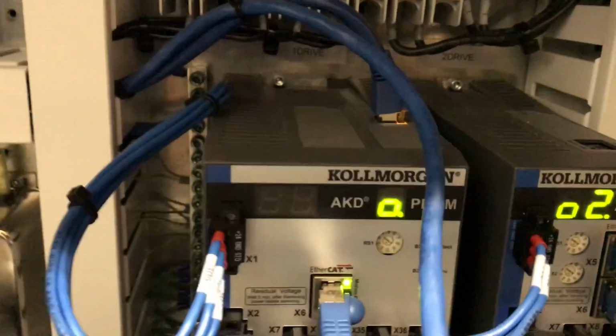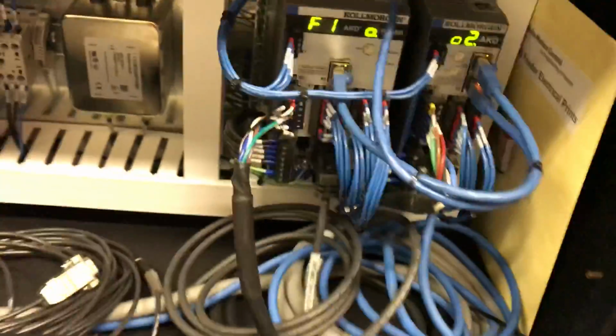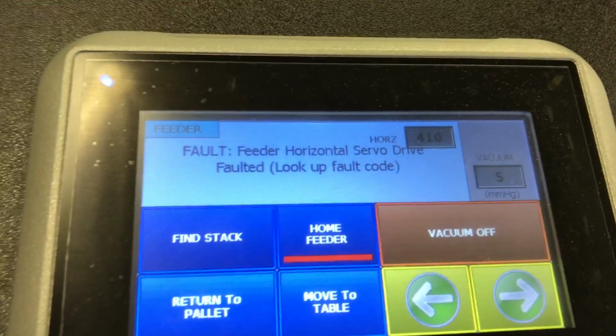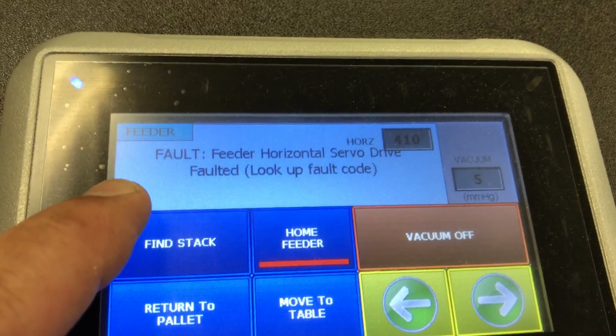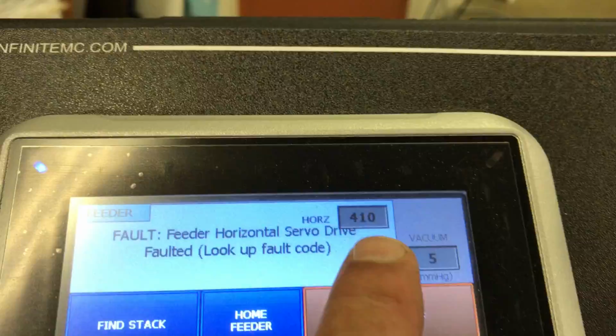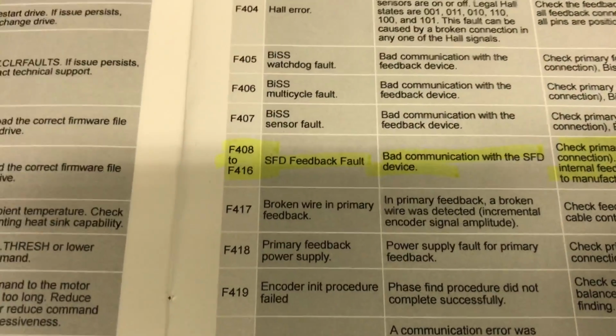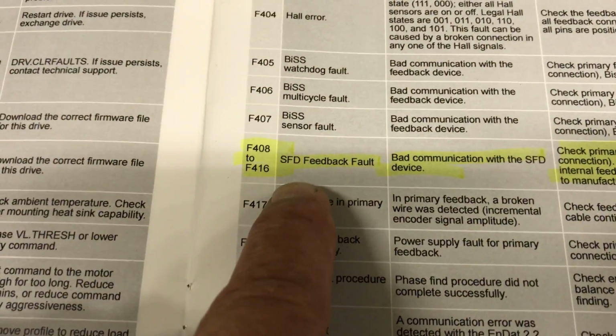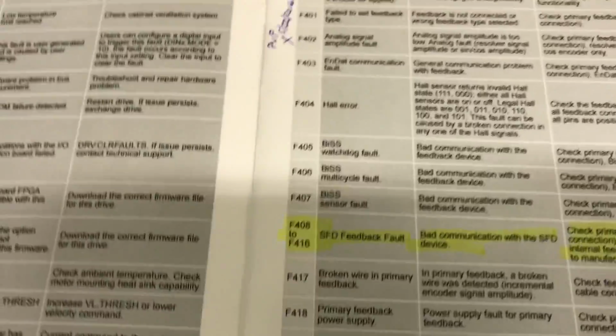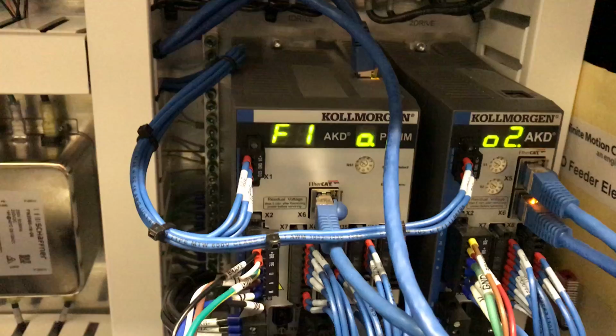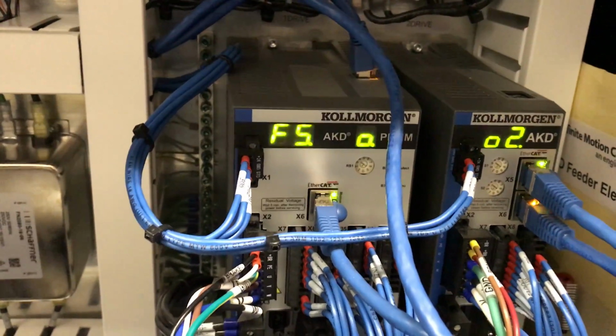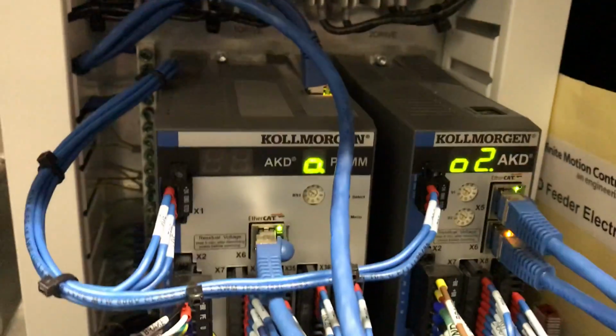So we see the fault on the drive, but we should also see the fault on the touchscreen, and as you can see, it says horizontal servo drive faulted, and we have a fault 410. Now 410 doesn't match up with 415, but if we look in the book, 410 does fall in this range. It is the SFD feedback fault, smart feedback device fault. So that's how we can tell what's going on with these drives, what the fault is, and it should lead us or give us clues into how to repair it.